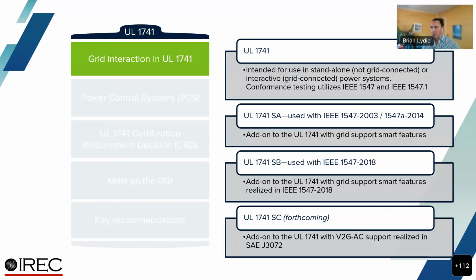And so that new version is also edition 3, and it's good to realize that once those additions to SB were published in September, they changed the edition of UL 1741 from edition 2 to edition 3, to make it easy to determine what version of the SB the products were tested to. So just to make sure everything's in compliance with the newest requirements, it should be compliant with edition 3.